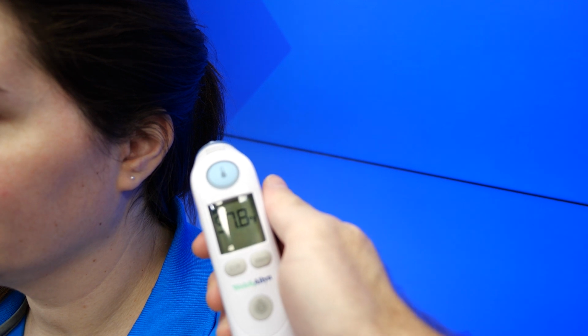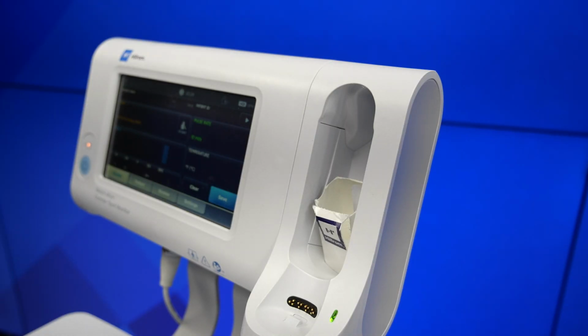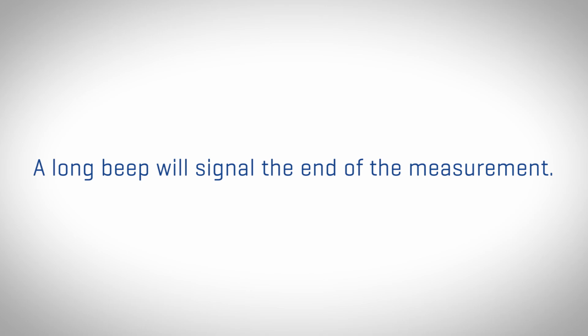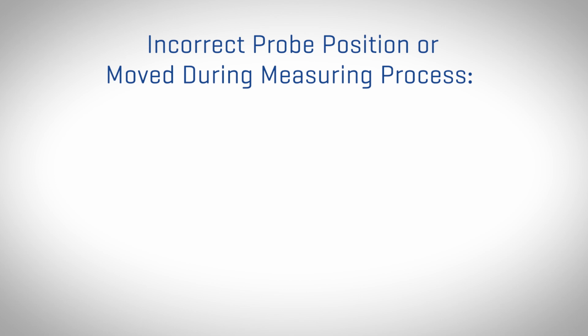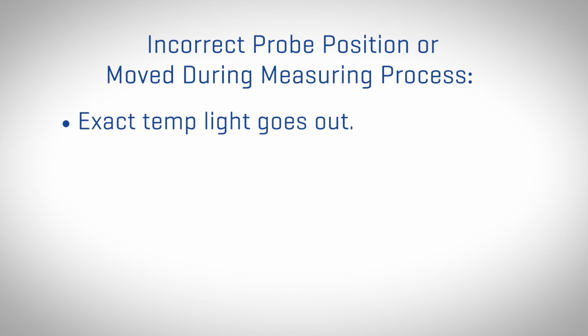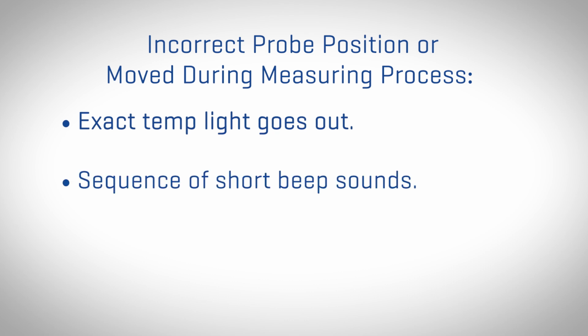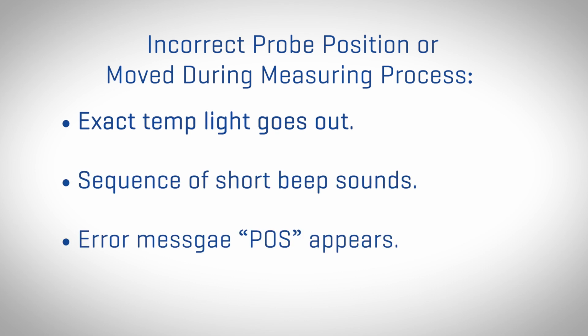If the probe is positioned correctly in the ear canal, the exact temp light flashes. When the thermometer detects an accurate measurement, the exact temp light is continuously on. A long beep signals the end of the measurement, and the display shows the result. If the probe is positioned incorrectly in the ear canal, or is moved during the measuring process, the exact temp light goes out, a sequence of short beeps sounds, and the error message POS, or position error, appears.